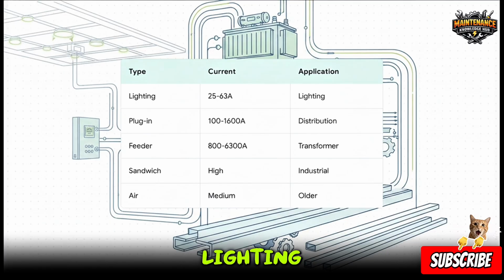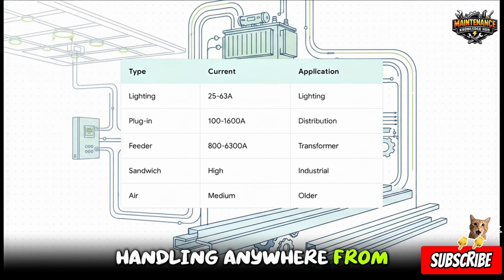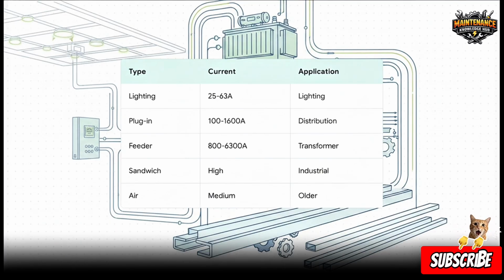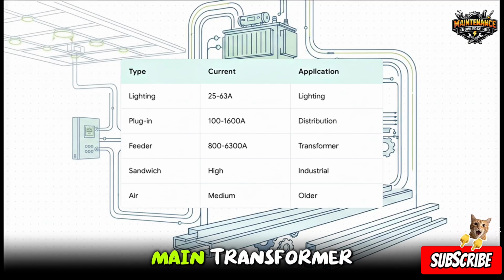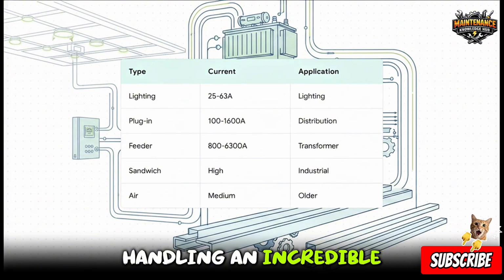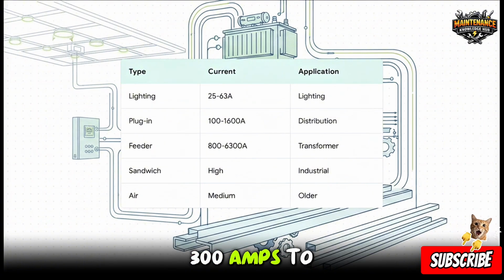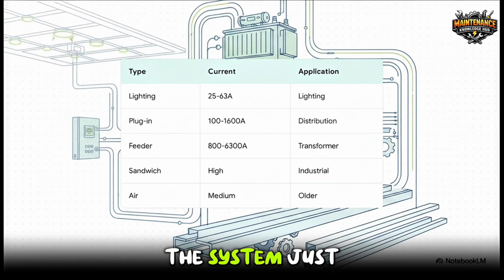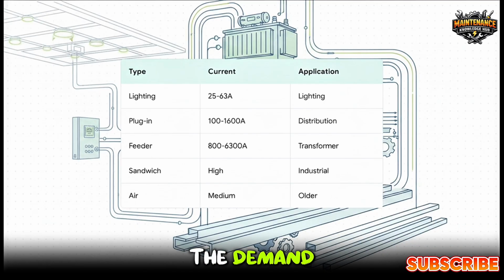The best part is how the design adapts perfectly to specific, real-world needs. For basic overhead lighting, you've got lighting bus bars handling anywhere from 25 to 63 amps. General floor distribution uses plug-in bus bars, pushing up to 1,600 amps. But when you need to move massive amounts of power directly from a main transformer, that's where feeder bus bars come in, handling an incredible 6,300 amps. To put that into perspective, that is enough current to power hundreds of average homes at the exact same time. The system just scales effortlessly to the demand.